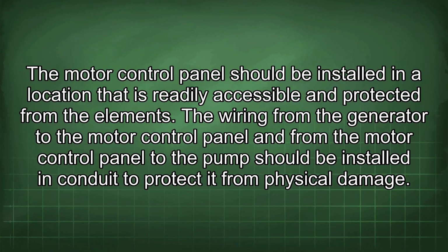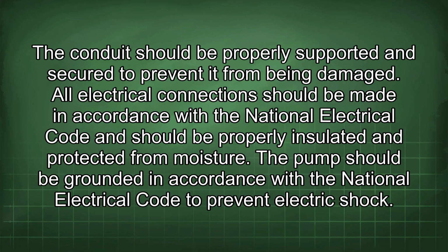The wiring from the generator to the motor control panel and from the motor control panel to the pump should be installed in conduit to protect it from physical damage. The conduit should be properly supported and secured to prevent it from being damaged. All electrical connections should be made in accordance with the National Electrical Code and should be properly insulated and protected from moisture. The pump should be grounded in accordance with the National Electrical Code to prevent electric shock.